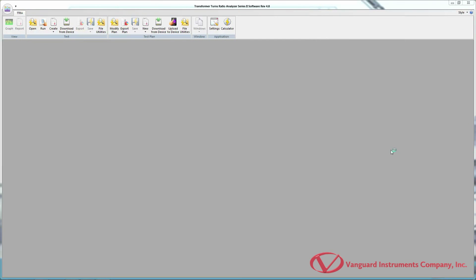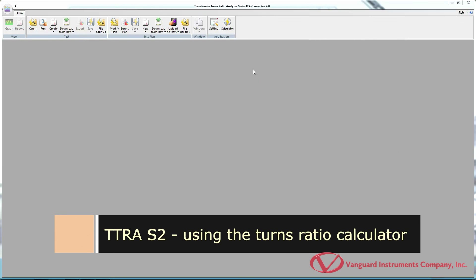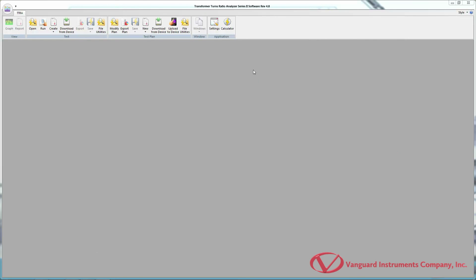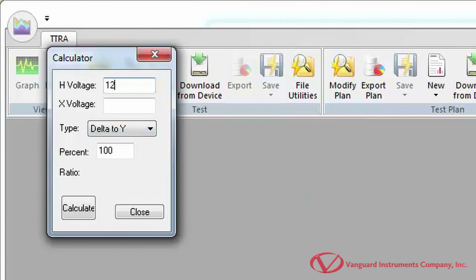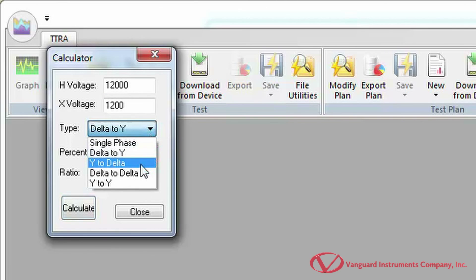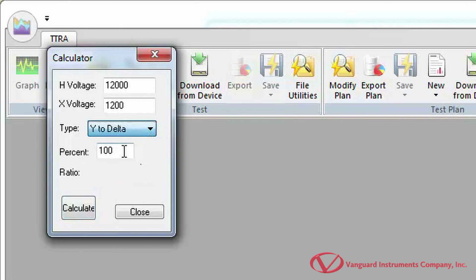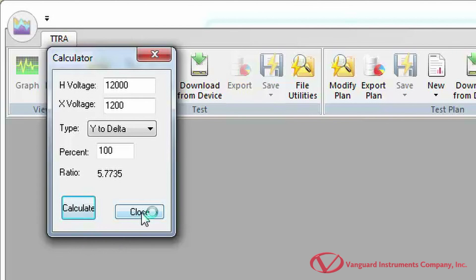The last feature of the TTRA-S2 software we'll look at is the Simple Turns Ratio Calculator. To use the calculator, click the Calculator icon in the Application command group. Enter the H and X voltage values, then select the transformer type from the drop-down menu. If desired, type a percentage value in the Percent field — this calculates the turns ratio at the specified percentage of the nameplate voltage. Click Calculate and the turns ratio value will be displayed. Click Close to close the calculator.